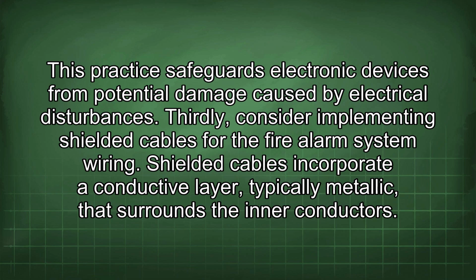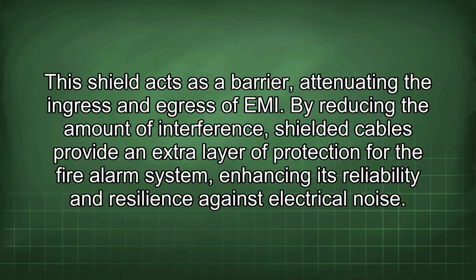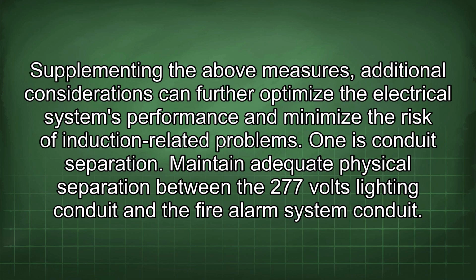Thirdly, consider implementing shielded cables for the fire alarm system wiring. Shielded cables incorporate a conductive layer, typically metallic, that surrounds the inner conductors. This shield acts as a barrier, attenuating the ingress and egress of EMI. By reducing the amount of interference, shielded cables provide an extra layer of protection for the fire alarm system, enhancing its reliability and resilience against electrical noise. Supplementing the above measures, additional considerations can further optimize the electrical system's performance and minimize the risk of induction-related problems.